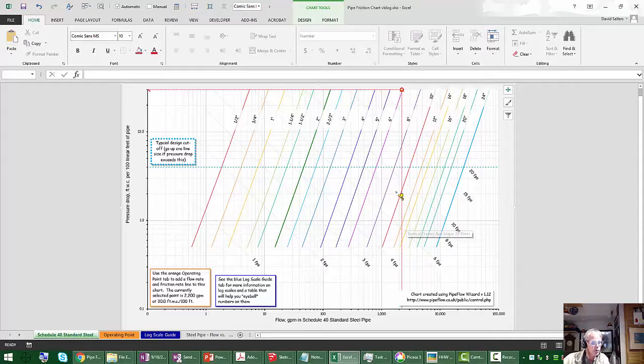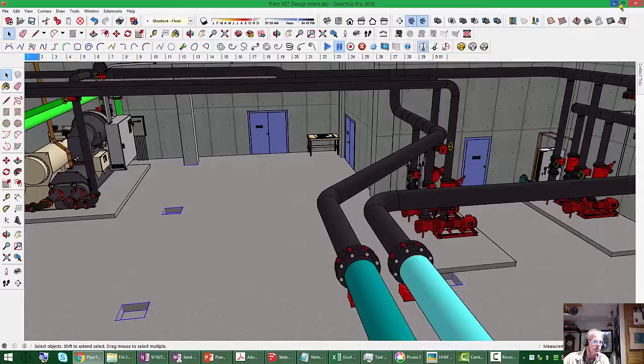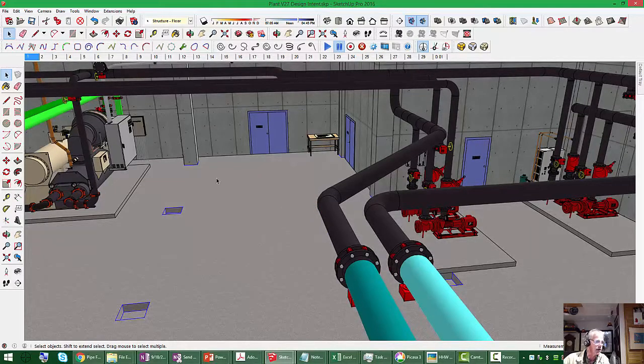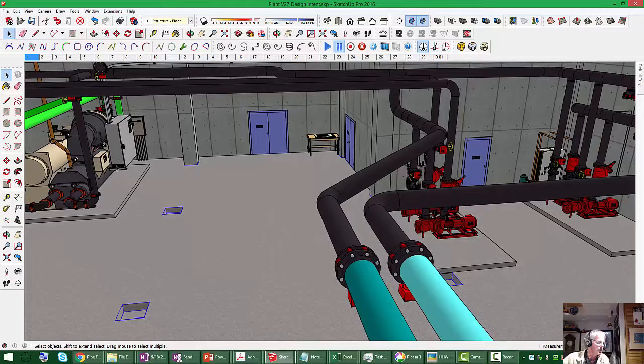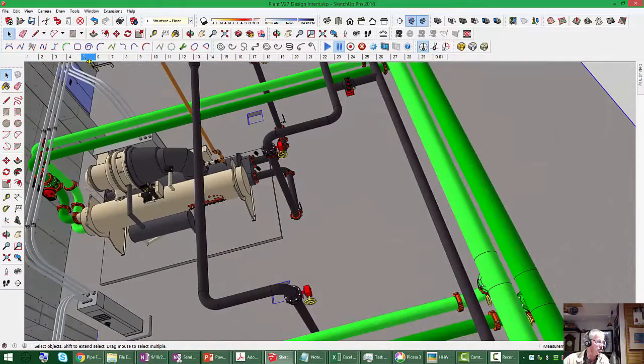Okay, so those are the field clues you could use to understand what the peak capacity on this plant might be intended to be, and if the chillers are supposed to run together or not. Okay. Now the other question I asked you is, what do you think the capacity on the chillers is right now? In other words, what's the tonnage on these chillers right now? There's a couple ways that you could do that. Basically, the first thing would be to say, well, how many of them are running? Are any of them running, in fact?